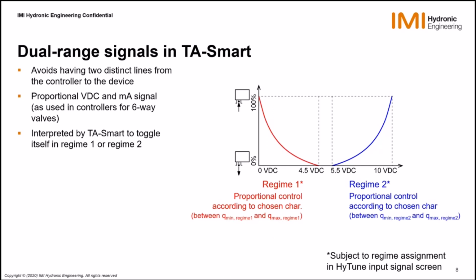You get a second area, which is regime 2, where we do exactly the same as for regime 1, but according to different maximum and minimum value. And the fact that regime 1 is on the low voltage and regime 2 is on the high voltage is only a default situation. You will see that in the input signal screen, you are able to reverse this assignment of regimes, because it might very well be that the people have programmed their controller in the opposite way, and therefore we need to adapt, and the quickest is simply to go in the app and switch between regime 1 and regime 2, so associate regime 1 to the high voltage and regime 2 to the low voltage.